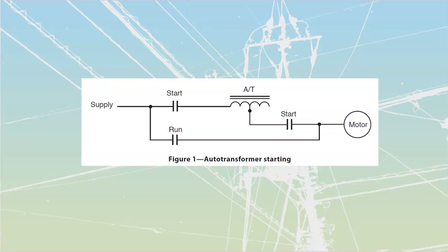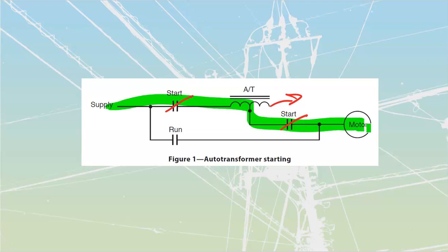In its most basic form, an autotransformer starter is going to look like something along these lines. Once again, we're going off of a one-line diagram where I'm going to have a start and a run position. What is missing here is obviously the fact that this is going to have to be connected into a Y type of point, along with 3 other ones, but they're only trying to show us a single line at a time. Under the start position, I would have a connection that would look like this. So I'm going through part of my winding, transforming down in order to get my motor value of voltage.